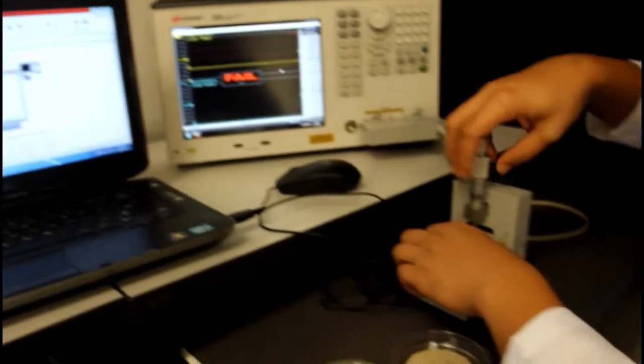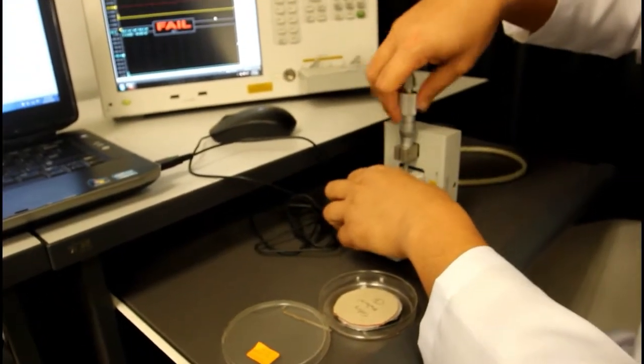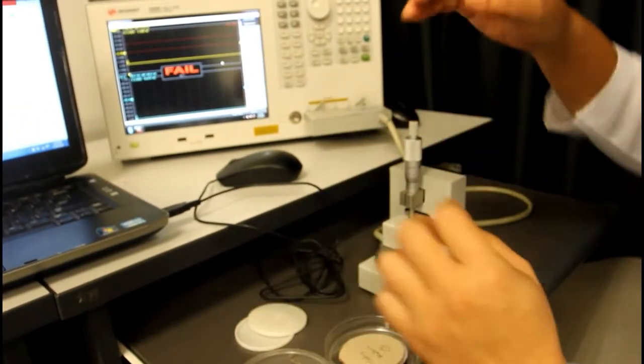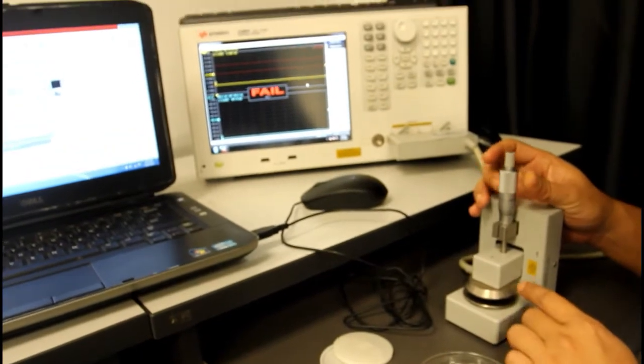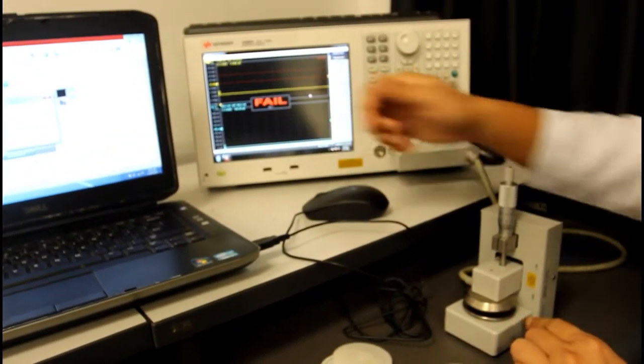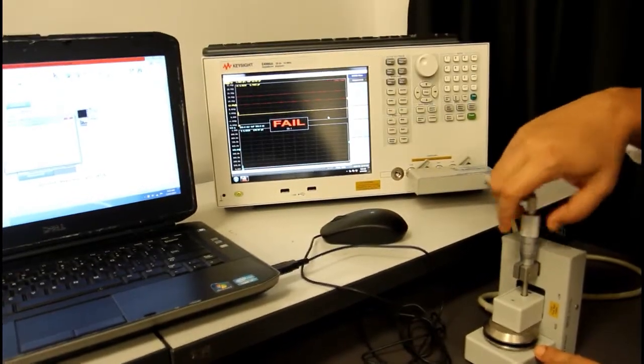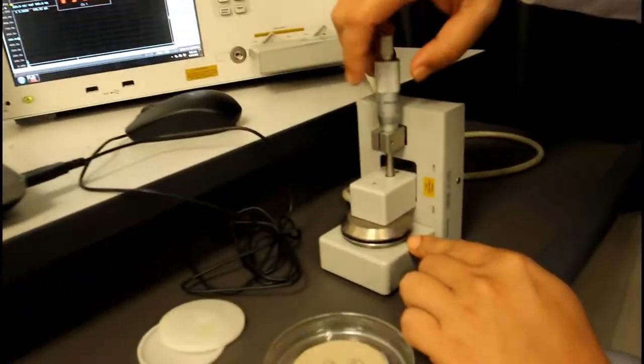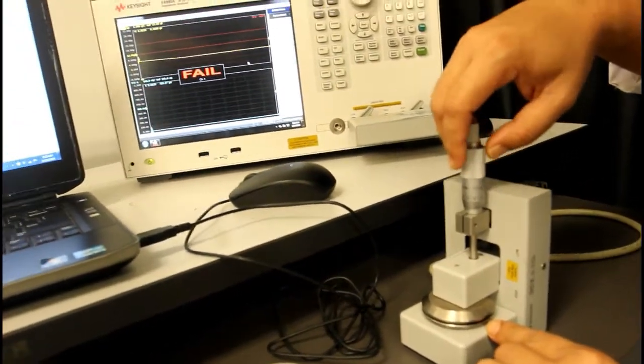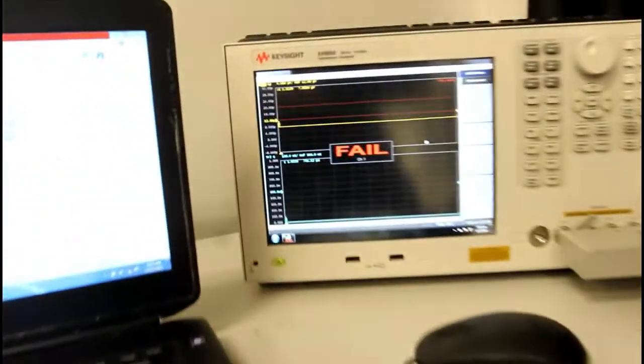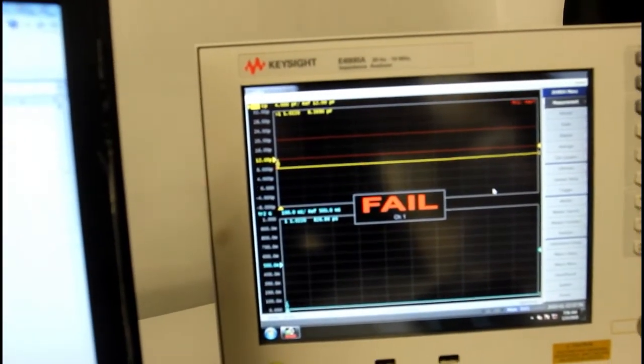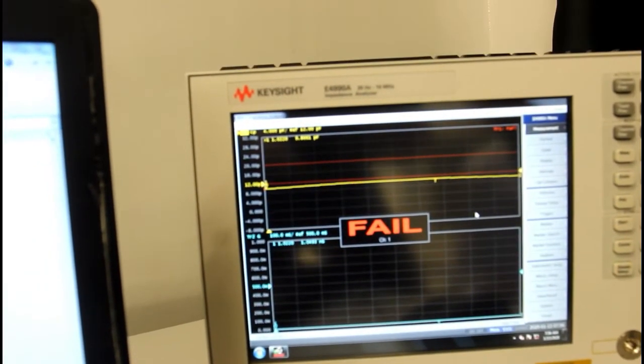Click on Next Setup. Then click on OK. So, now you can see that the graph on the screen of impedance analyzer is in failed position. So, what you need to do is, tune the fixture until the yellow line in your impedance analyzer screen is in between the red line. Suppose when the yellow line is in between the red line, the words of fail will disappear.